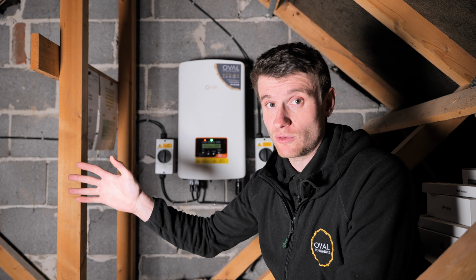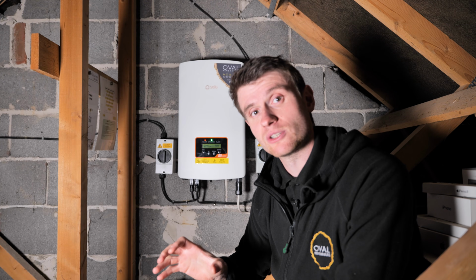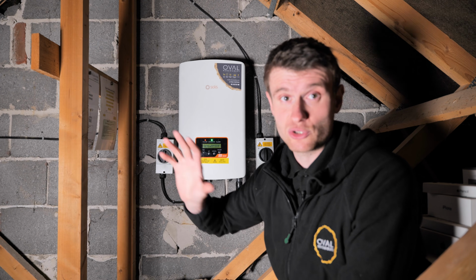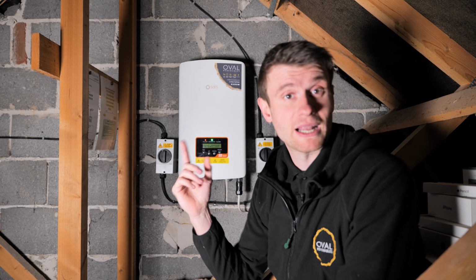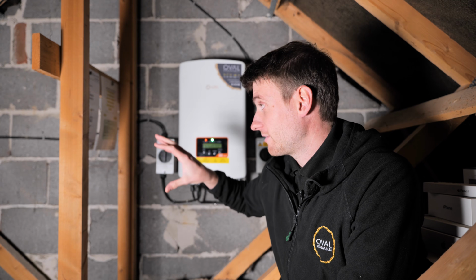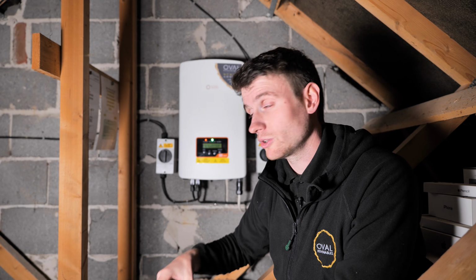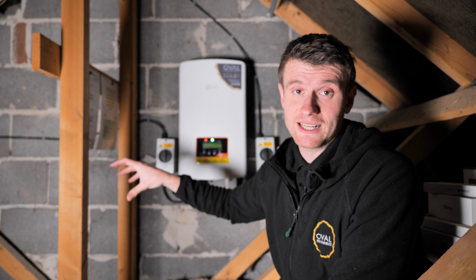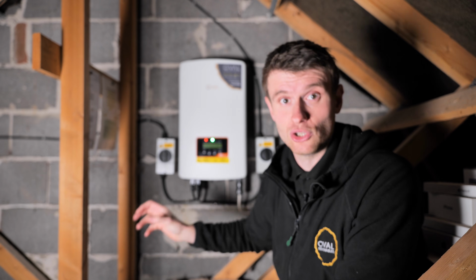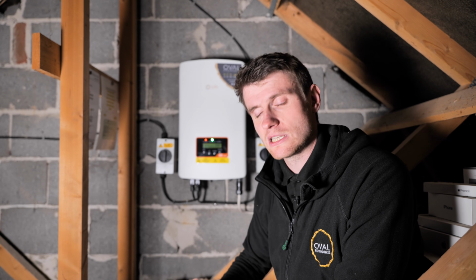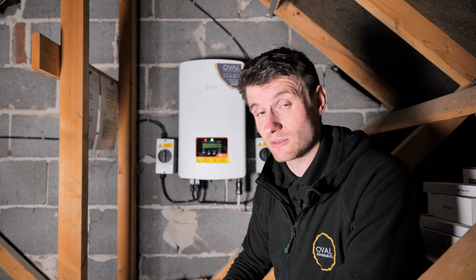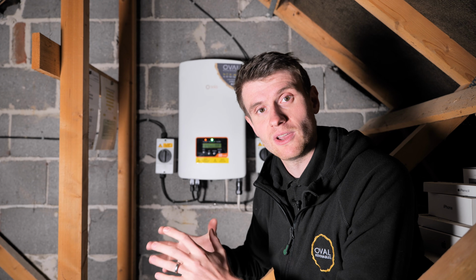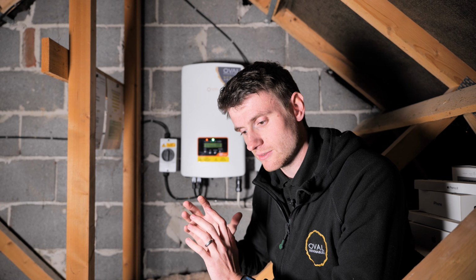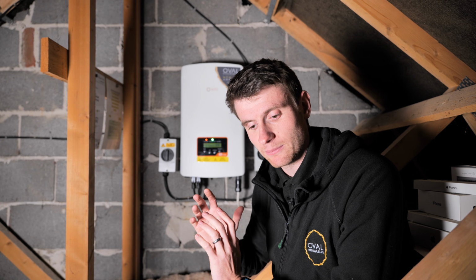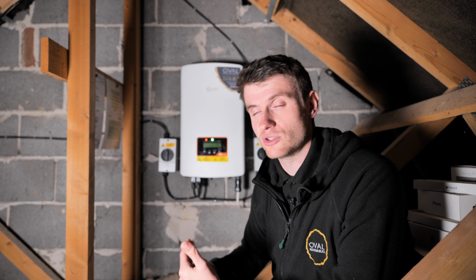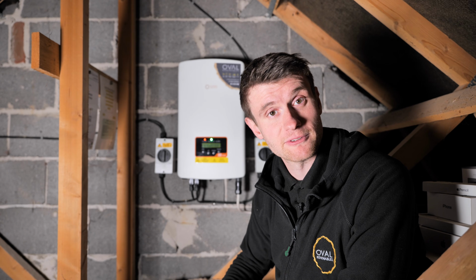You can add more panels to your roof, but you can't put that through the generation meter. So say this roof was double the size - you could put the same amount of panels on again, but you'd have that either feeding directly into the Libbi we've installed, or feeding directly into a second inverter that doesn't go through the generation meter. There's lots of things you can do, you just have to make sure you're not increasing the generation capacity of the feed-in tariff registered system, because then you'd drop onto an estimated feed-in tariff.